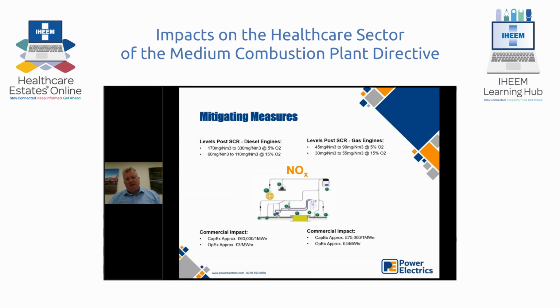With regards to gas systems, it's a little bit more expensive because the SCRs tend to be a little bit bigger, so you're probably looking at around £75,000 a megawatt and about £4 a megawatt hour operation, because you're burning a little bit more AdBlue, and that's one of the consequences of it as well.